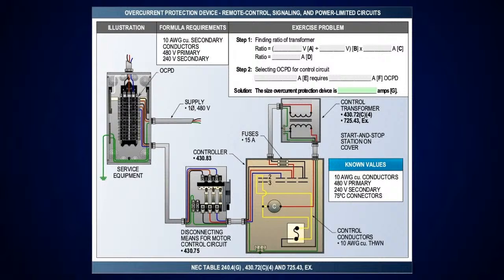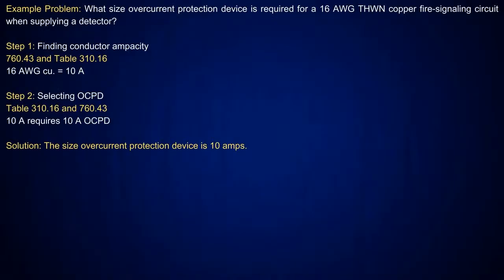In this one here, you've got number 10 conductors, okay, with a 480 volt primary and 240 volt secondary. So divide the 480 by the 240 volt and get the amperage of the number 10. That'll give you the amperage, and then drop down to your next standard size. All right. And then we're getting close to finishing this up. This is awesome. Now we're going to look at a fire alarm signaling circuit.